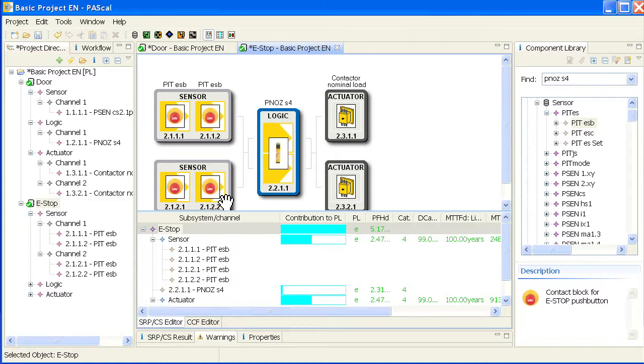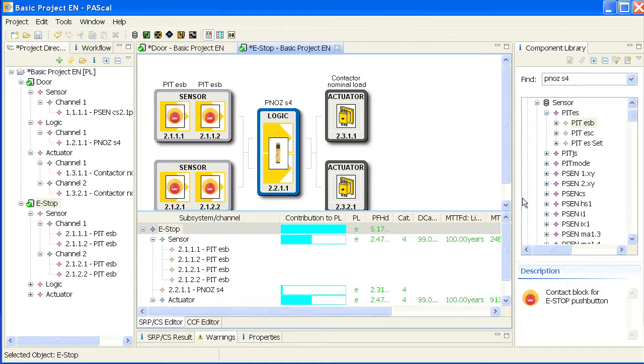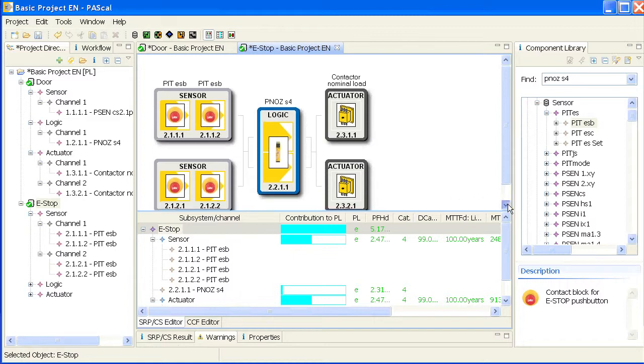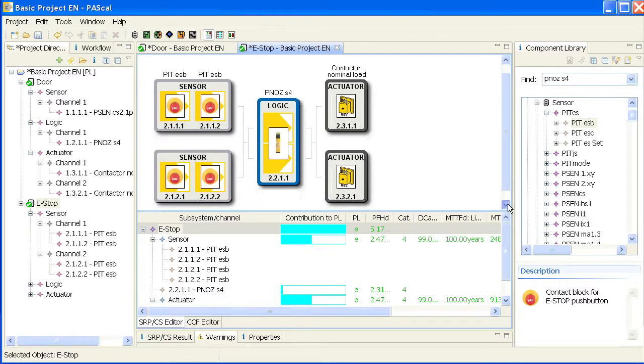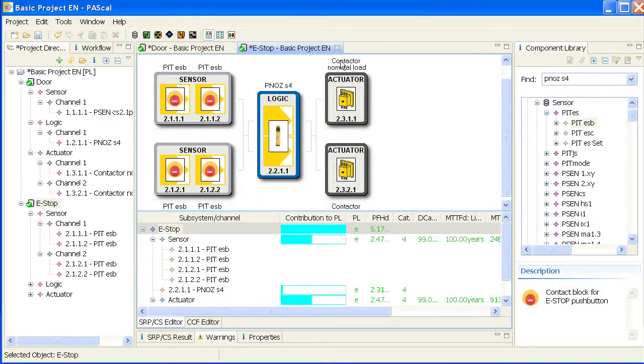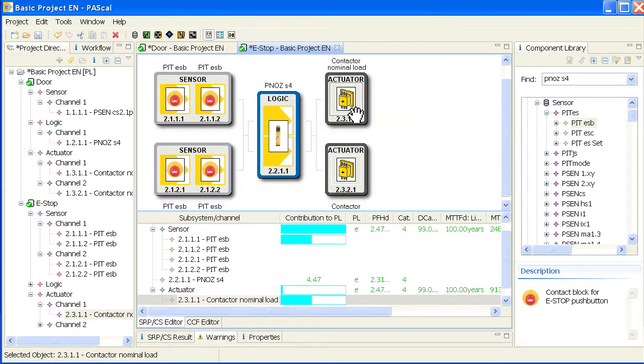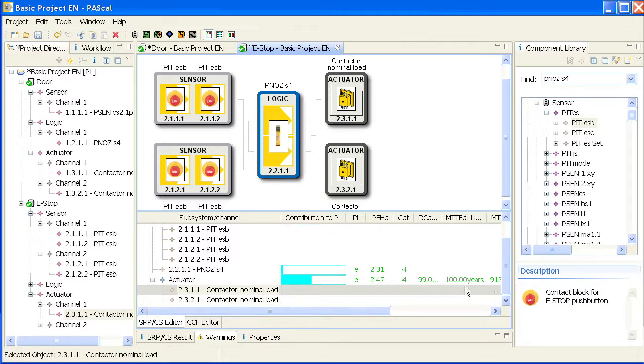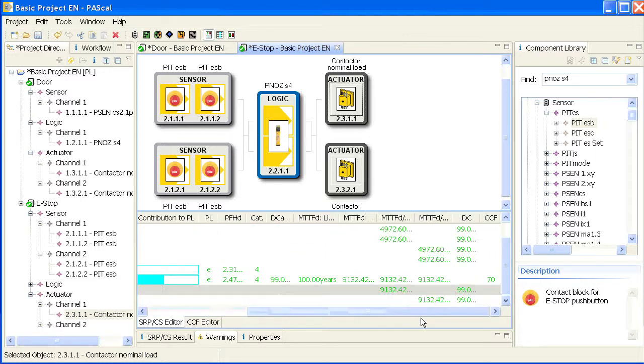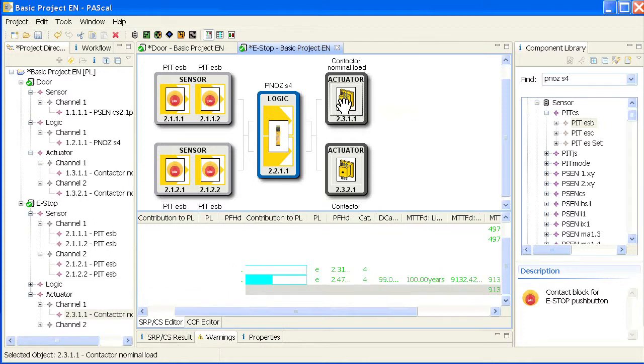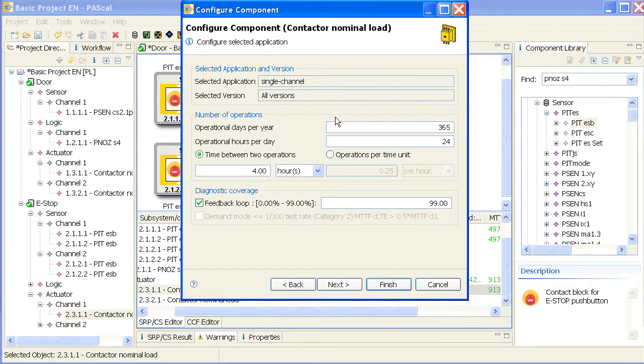So you've seen a number of options and I want to mention one limitation which is not due to Pascal but due to the standard. You'll find here a relay which has a b10d value. You see it down here. It's listed as an MTTF value which derives from a b10d. Of course I have to enter the number of activations.